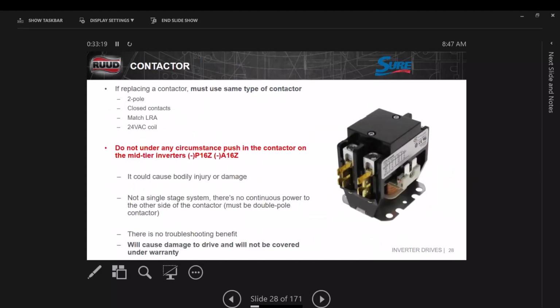This is the contactor. Notice it's sealed, but it does have screws that can be removed. If you change this contactor, we need you to go back with the same exact contactor. We want it covered, right? And we want a 2-pole contactor. And again, you're going to see this a lot. Under no circumstances do we ever push that contactor in. It could and will possibly cause bodily injury, and it's going to kill the board. Once damage is done to the board, it can't be repaired. It has to be replaced, and that wouldn't be covered under warranty.